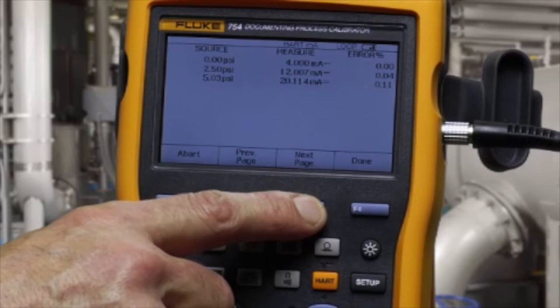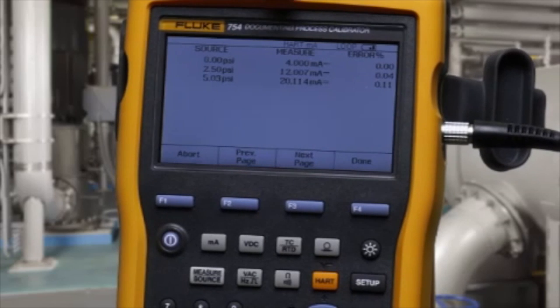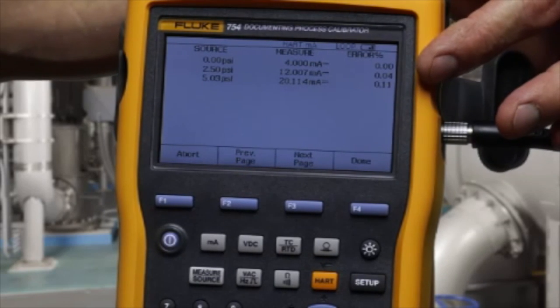Apply. Test is complete. You see the applied pressure measured milliamp. In this case, all the errors are less than 0.25% and the test passes.